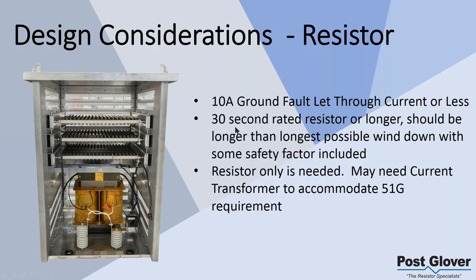You're going to want to have this resistor rated for the entirety of the wind down of the generator. So you want to make sure that the entire thing is completely shut down and stops before your resistor gets to its max temperature, essentially. So I would recommend 30 seconds just based off of that, because your wind downs can be long. But if you have a scenario where your wind down only takes 3 seconds, you understand the idea. You just need to make sure that it's long enough that it addresses the wind down.